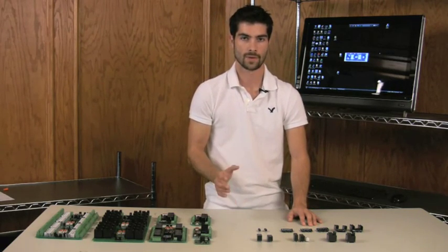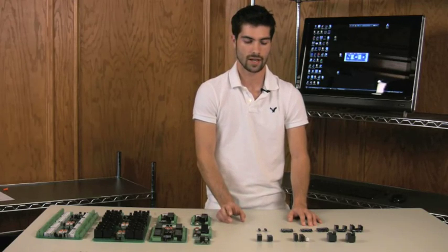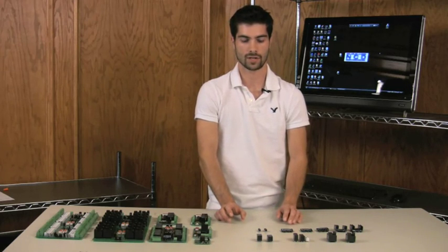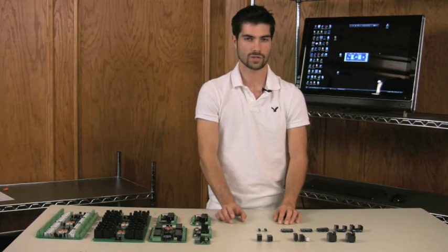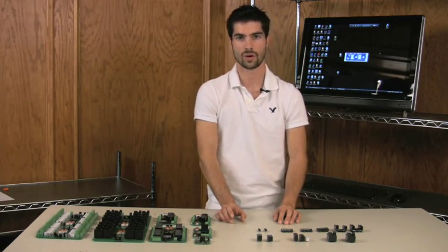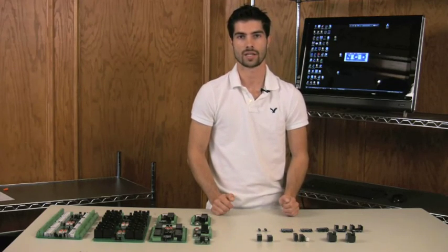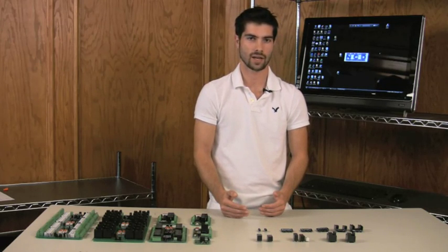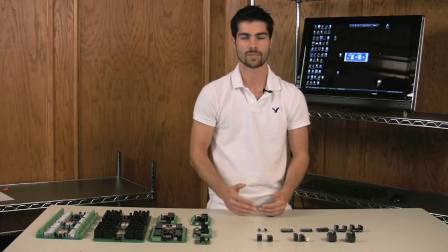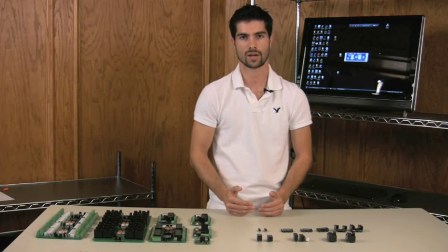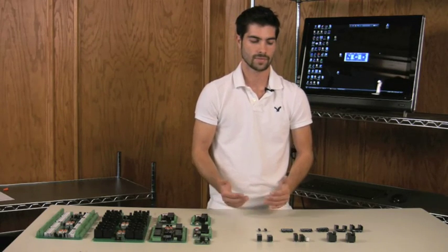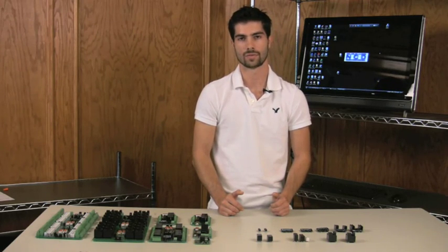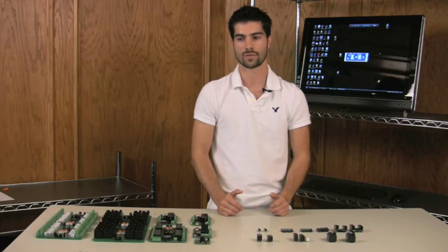If I have a pump, which is an inductive load, and it's rated at 5 amps, I'm probably not going to use a 5 amp relay. I'm probably going to use a 10 amp relay. It usually doesn't cost a lot more to overrate the relay, and it will expand the relay's life. So if you're at 3 amps, use a 5 amp. If you're at 5 amps, use a 10 amp. For the most part, I recommend rounding up because that's really going to expand the life of your relay. So be sure you do that whenever considering a relay.